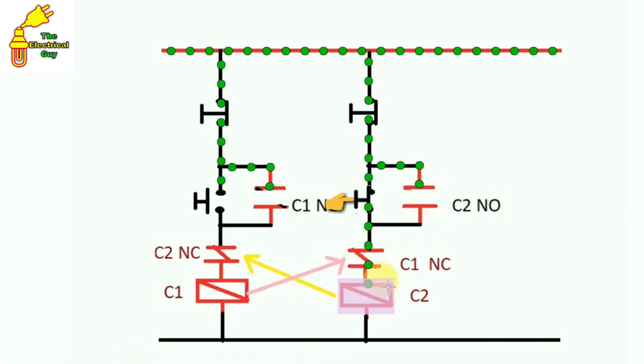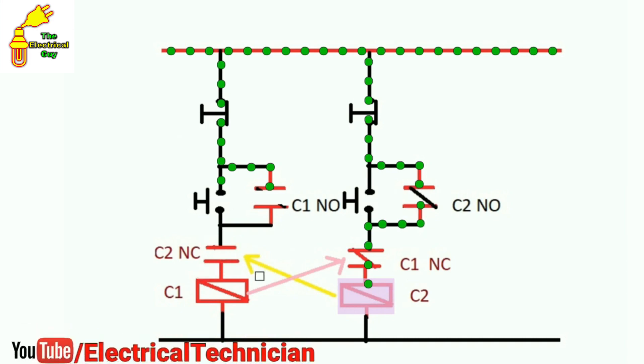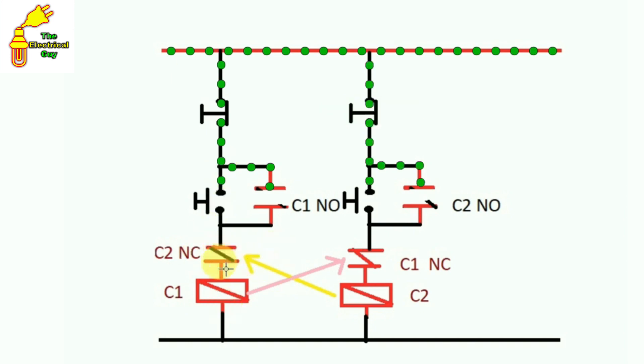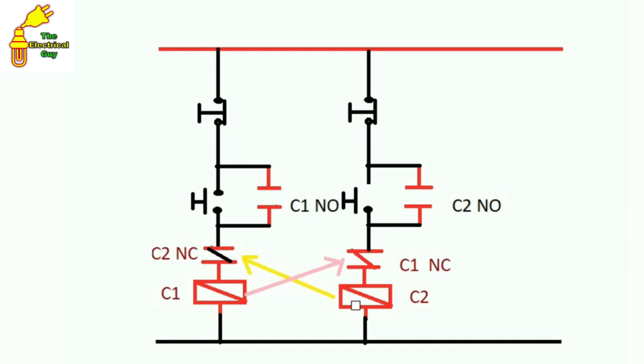Now if we press the start push button for C2, this circuit will be completed, current flows ahead and C2 contactor gets picked up. When C2 contactor picks up, two changes will occur. First, the auxiliary NO of C2 becomes NC. At the same time, the NC contact here becomes NO — it will be open here. So current will not flow from here even if we press the push button — this means C1 contactor will remain off. When we turn off C2, this becomes NO and the auxiliary contact again becomes NC, back to normal condition.